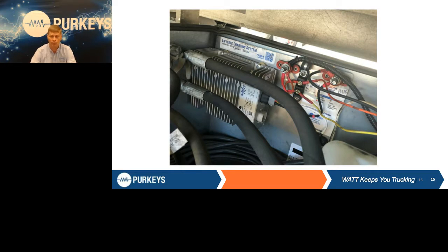Has road service, someone gotten here and done a repair? A lot of times we see our ends are not used. They'll use some generic crimp-on ends, which often don't provide the best connection and definitely aren't a very sealed connection. These battery boxes are prone to getting all kinds of road splash, and since you're near batteries, you can get some acid spray or acid from venting of the batteries. So you want to take a look at this.